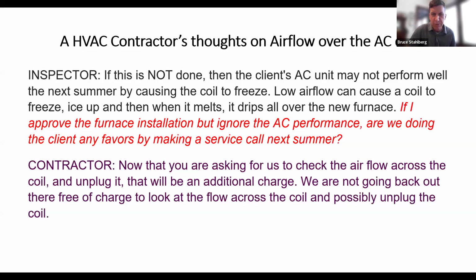Okay, so I talked to a lot of contractors, and this breaks all the rules of PowerPoint presentation with having this many words on there. But it was interesting because I called them up and I said, the airflow is really important on this. This one's got low airflow. Are we doing the client any favors? We might freeze the coil. And he said to me, now that you're asking us to check the airflow, there's going to be an additional charge for going back. The reason I put this in there is I thought, really, that's part of the system for setting it up. So we work with contractors now that they know we measure the airflow. Many of them have purchased a tool to do so, and we're trying to catch everything on the front end without reworks.